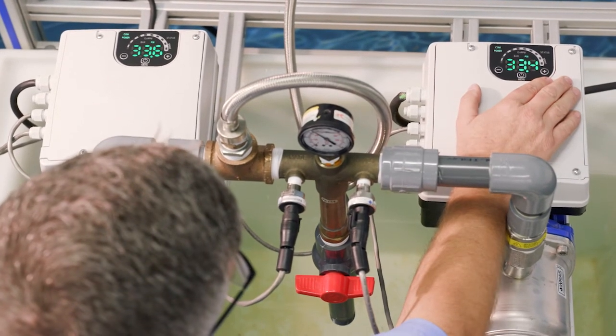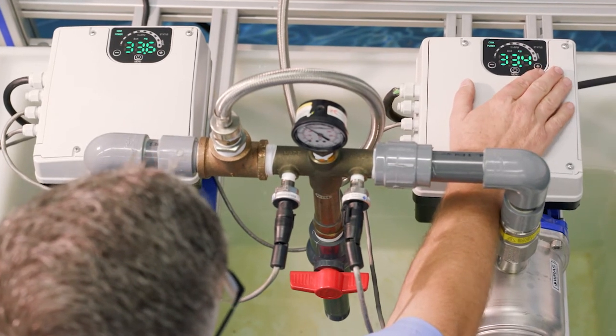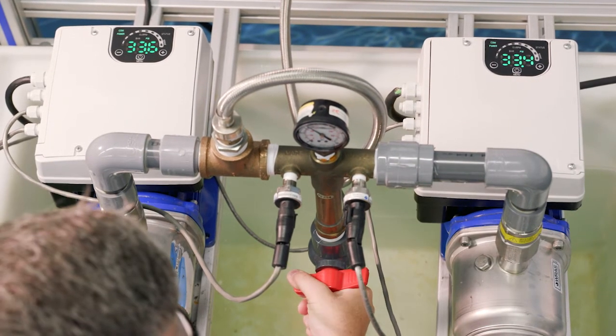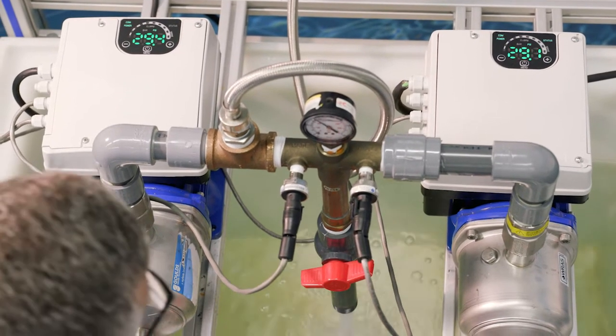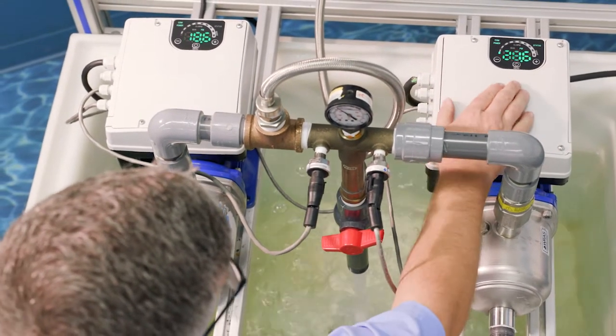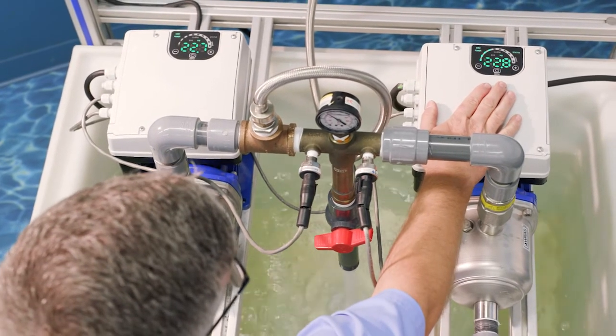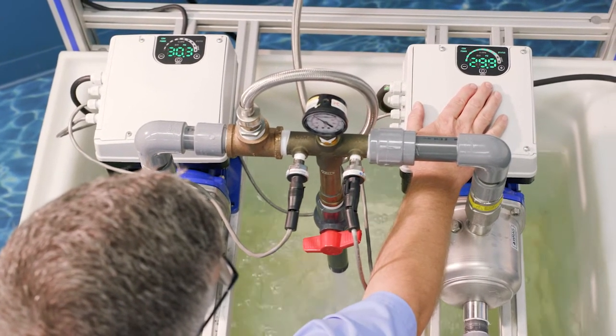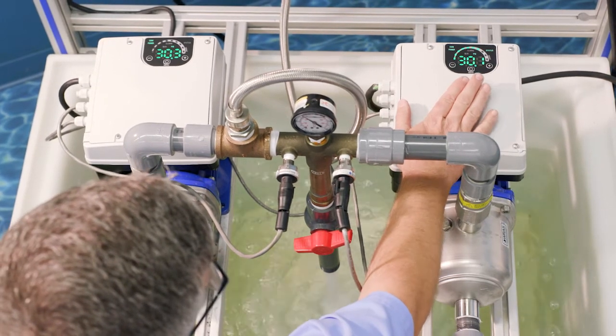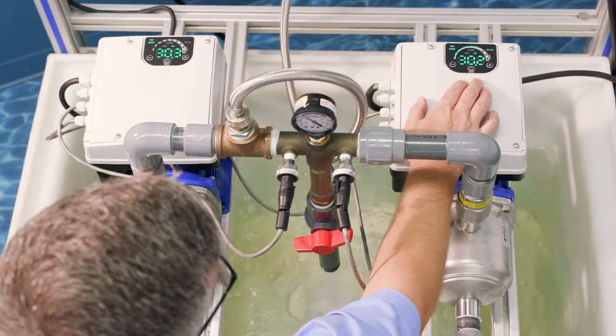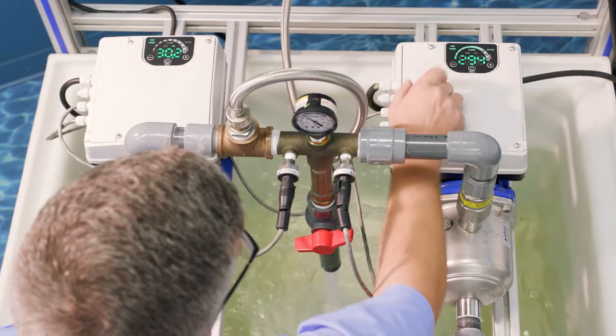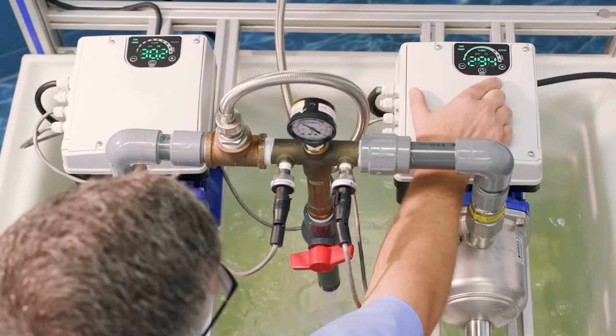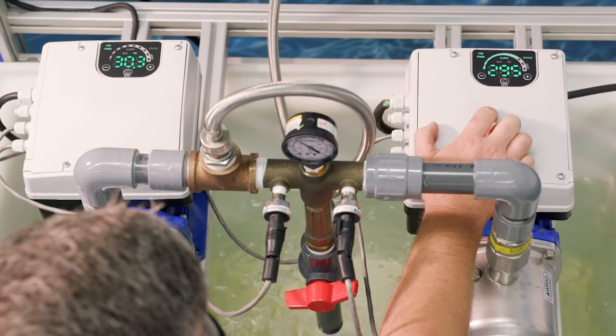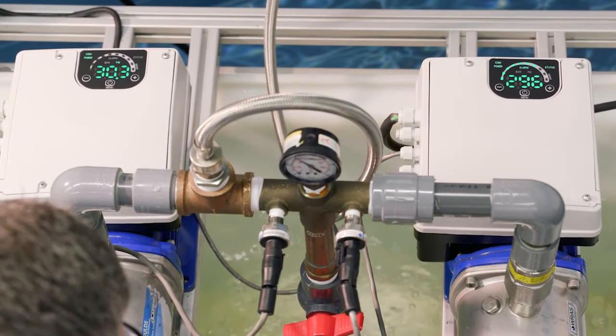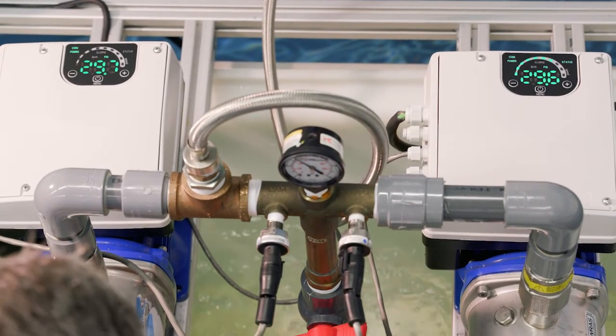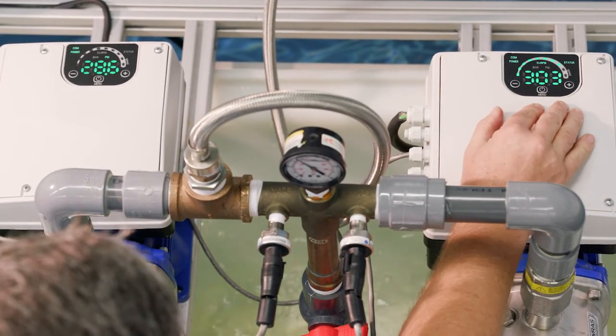So let's take a look and see if we can show you how that works. So we're going to give it some demand. So our lead pump hasn't changed because we have not hit the 24-hour time period for alternation. So our lead pump is keeping up with the demand. Let's just take a look at RPM again. It's not at full speed, it's maintaining the set pressure. So let's give it some more demand. Open up the valve. Take a look at speed again.